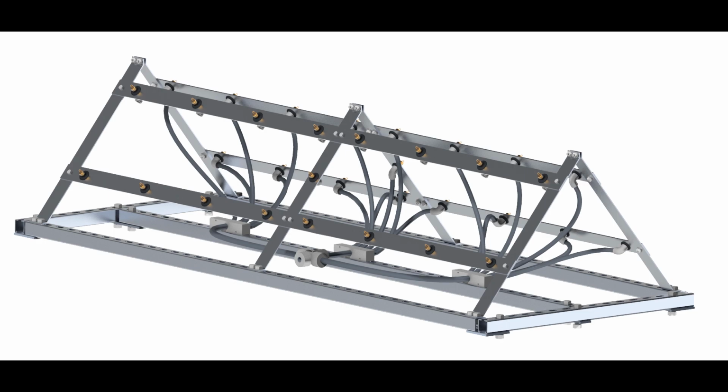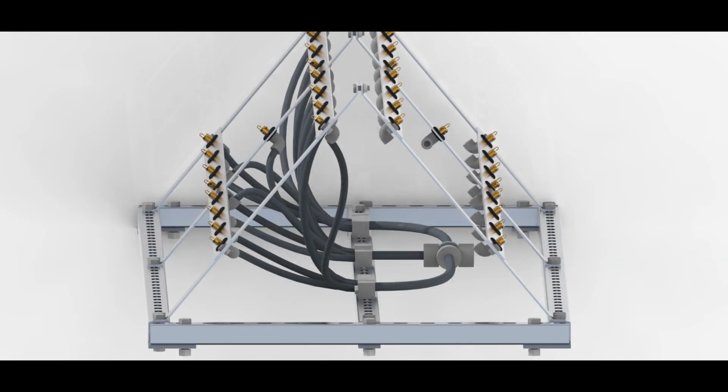This is the design our team ultimately decided will most evenly cover the majority of the condenser coil area with mist. A previous iteration was going to use sheets of aluminum, but it was challenging to follow through due to the design being too large and difficult to manufacture. For this reason, we decided to construct it from aluminum bars and steel strut channels. The array houses 17 nozzles on each side, which are evenly spaced to mist the most area possible. The plumbing was designed in parallel to ensure each nozzle sees the same exact pressure as the one before it.